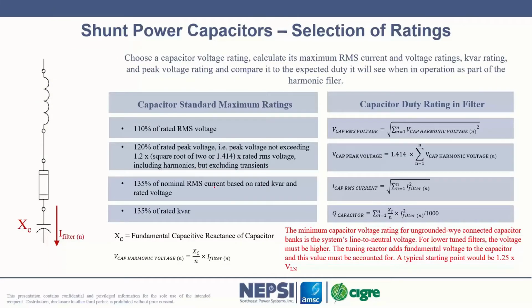So when you're doing your design, when you're choosing your capacitor, you're more or less taking your filter current at each of the frequencies multiplying times X of C. Remember, X of C drops with frequency, right? X of C drops with frequency. So as you go up to the second harmonic, the X of C is 1/2 its value. When you go up to the fifth, it's 1/5 its value at the fundamental. So you're calculating the voltage at various locations. You're calculating the peak voltage, and you're also calculating the RMS voltage using these formulas here.